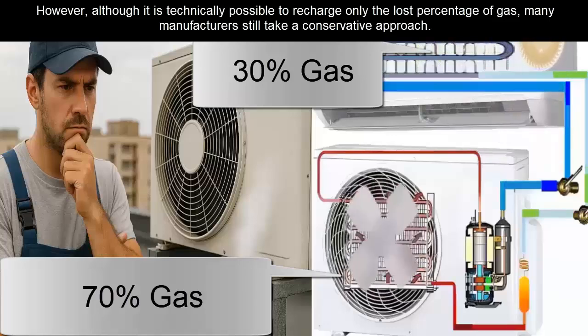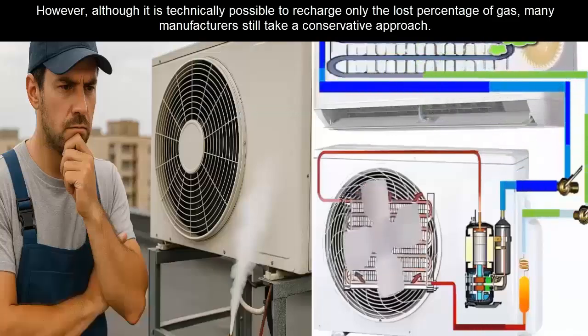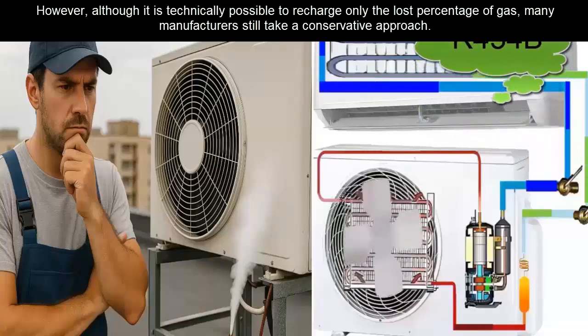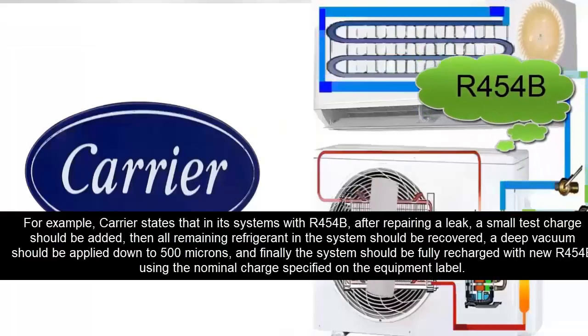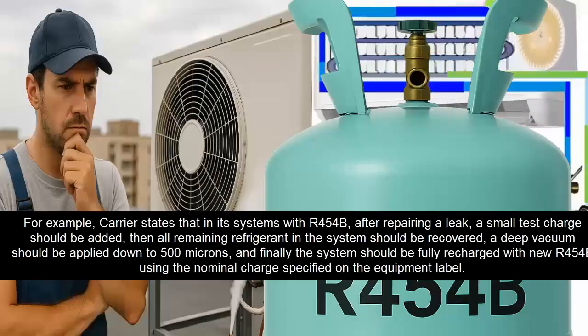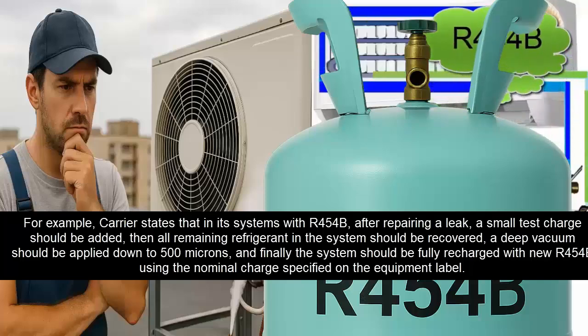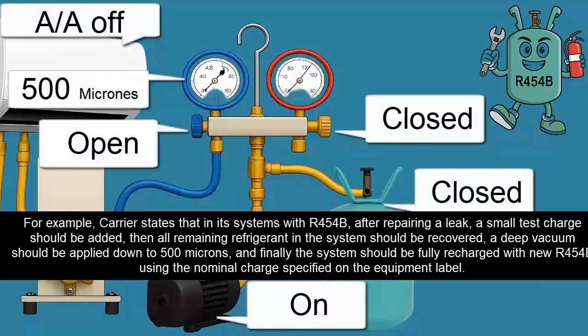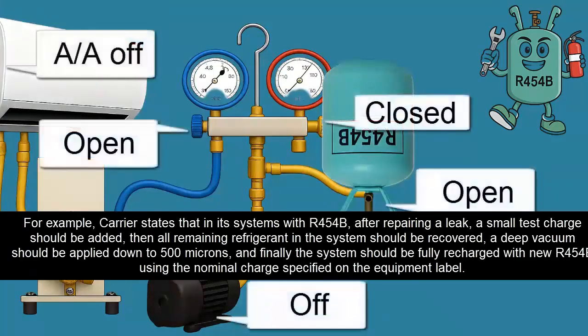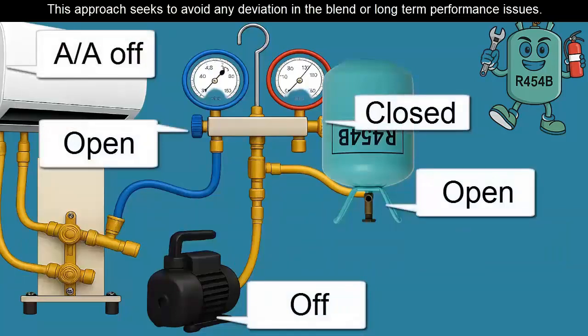However, although it is technically possible to recharge only the lost percentage of gas, many manufacturers still take a conservative approach. For example, Carrier states that in its systems with R454B, after repairing a leak, a small test charge should be added, then all remaining refrigerant in the system should be recovered. A deep vacuum should be applied down to 500 microns. And finally, the system should be fully recharged with new R454B using the nominal charge specified on the equipment label. This approach seeks to avoid any deviation in the blend or long-term performance issues.